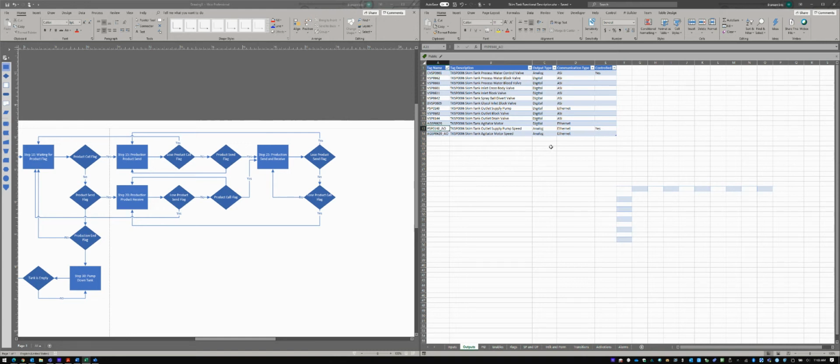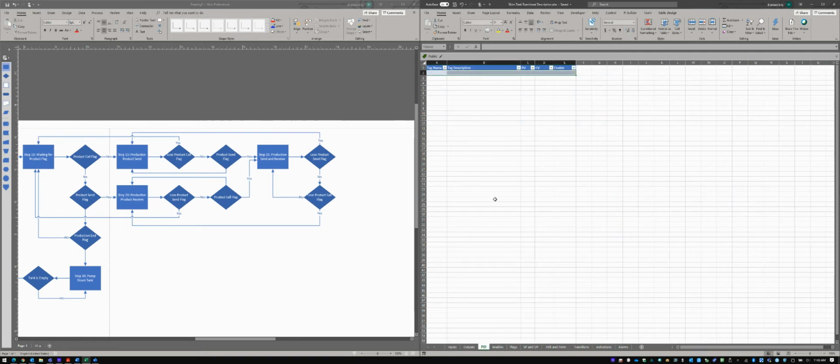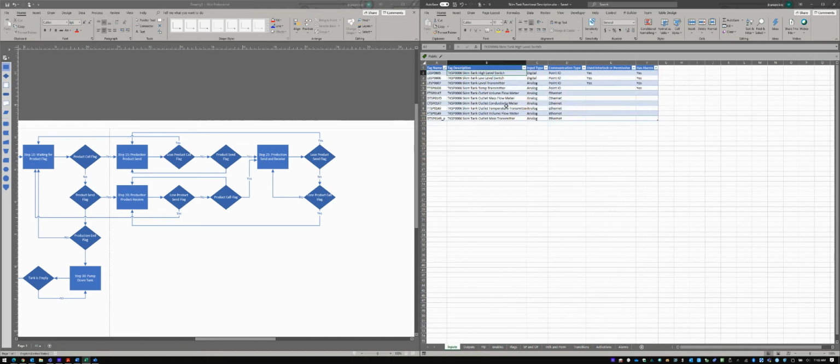So this pump speed is going to be controlled by a PID, and a PID is actually a pressure loop, but for the sake of just completing this all internally, we're going to use the flow. So we're going to call it a flow speed loop. So we're going to create a new PID here, and we're going to use the input, this flow, so the flow from the density meter.